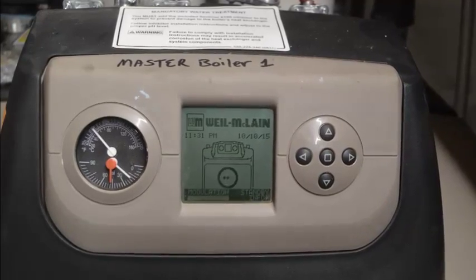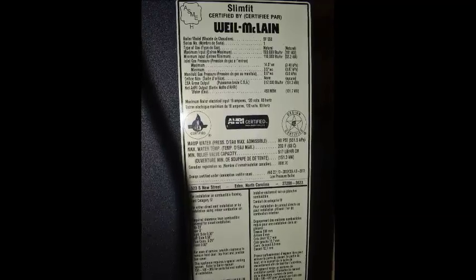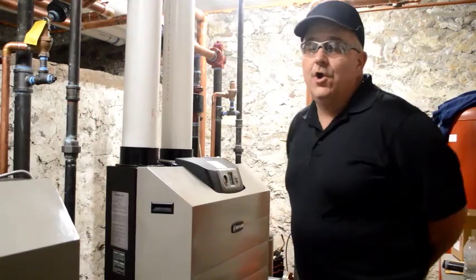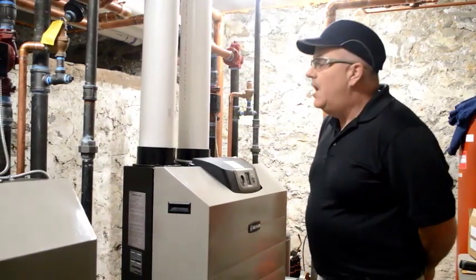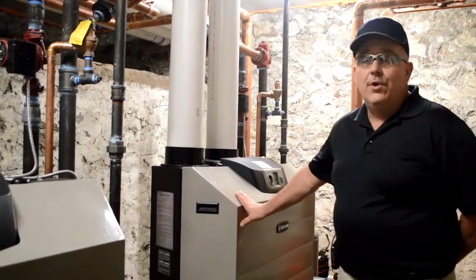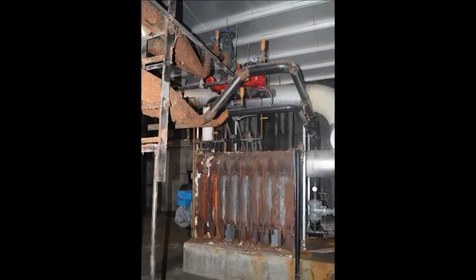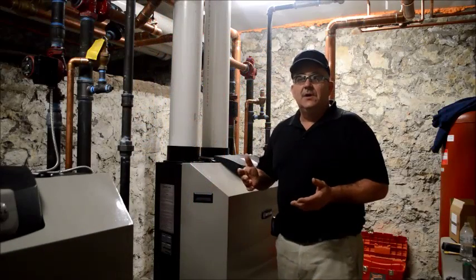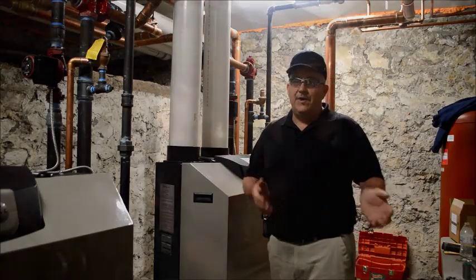We're in the church basement right now and we have two Weil-McLain 550,000 BTU modulating boilers controlled by a lead boiler. Depending on the load and the outdoor temperature, it will bring on the other boiler. Most of the time the system will operate under one boiler, with a huge savings to the church with their gas consumption. The original boiler would always fire at the same rate — like putting your foot on the gas pedal all the way to the floor every time you had to go 25 miles an hour.